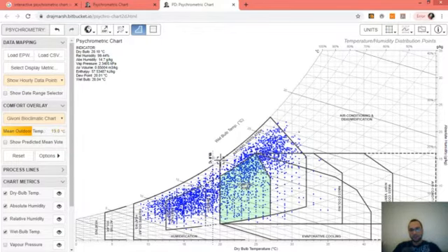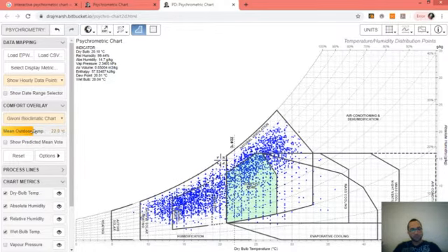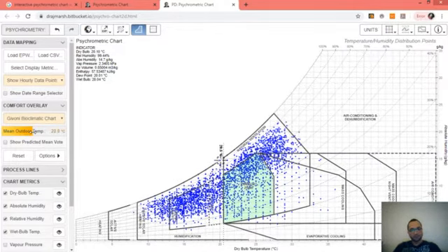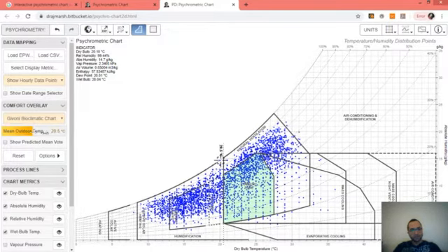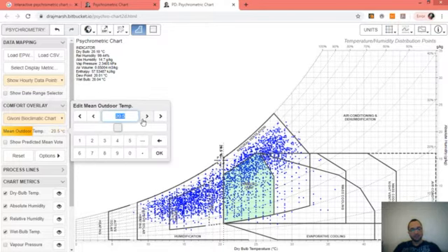For sure, the allocation of the zones depends on the average yearly temperature, which is not 19 degrees in Beirut. You need to change the value to the correct value, and actually it's 21. I have already calculated the value for Beirut. It's 21, the average yearly temperature in Beirut.